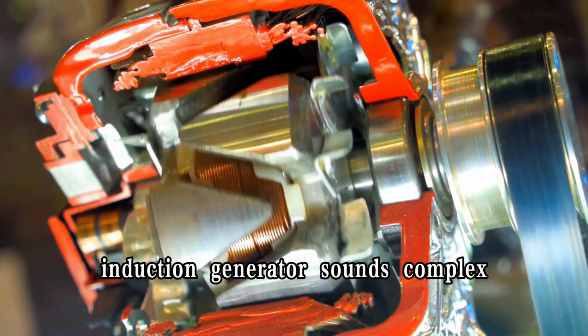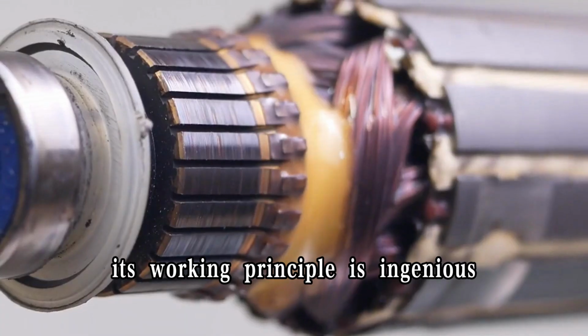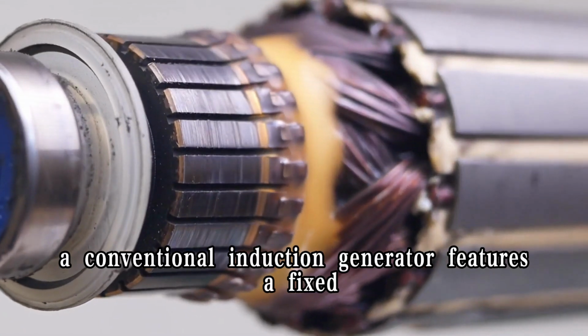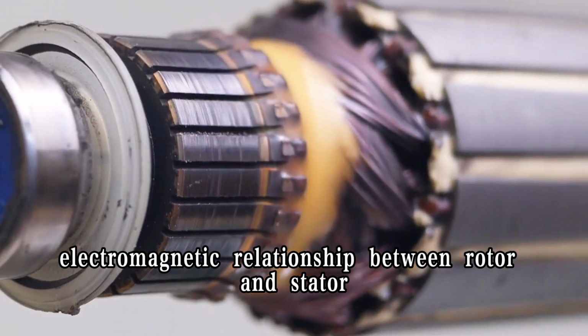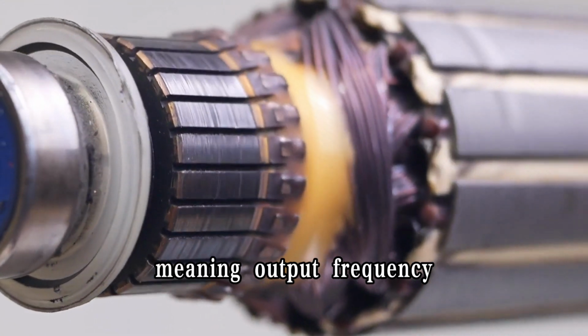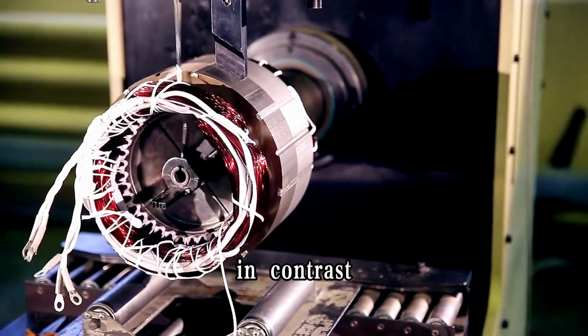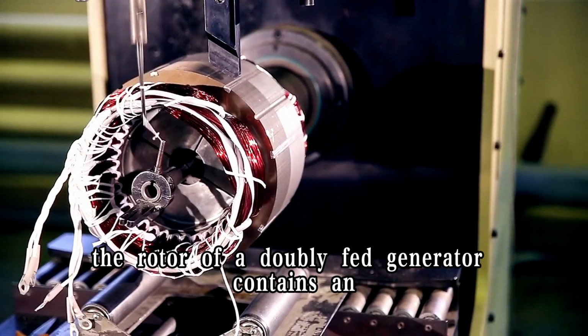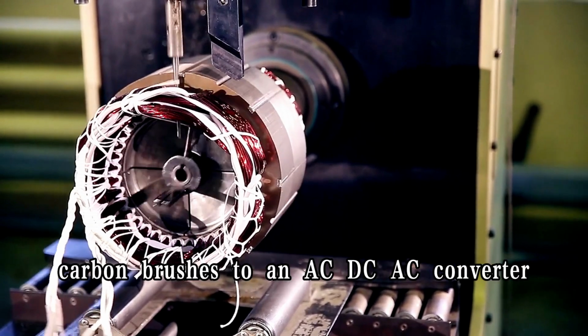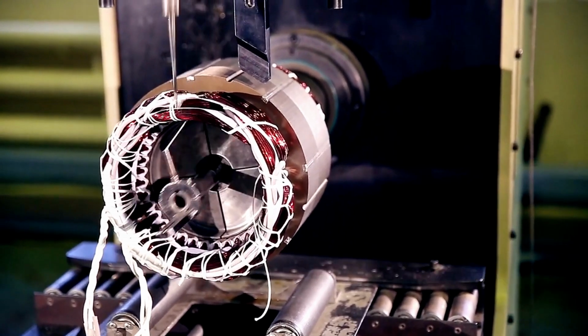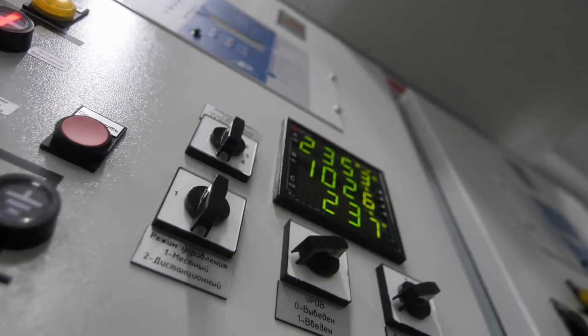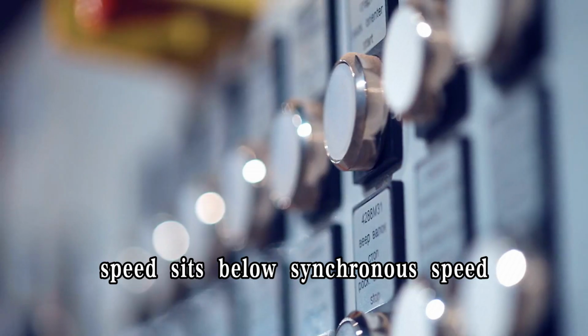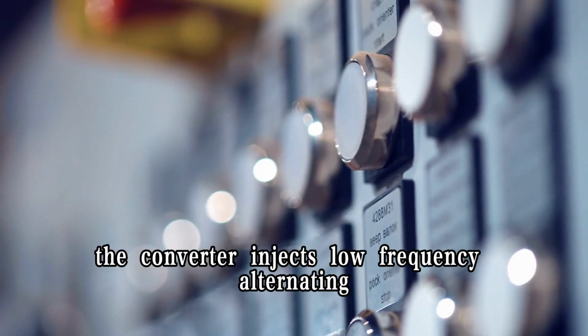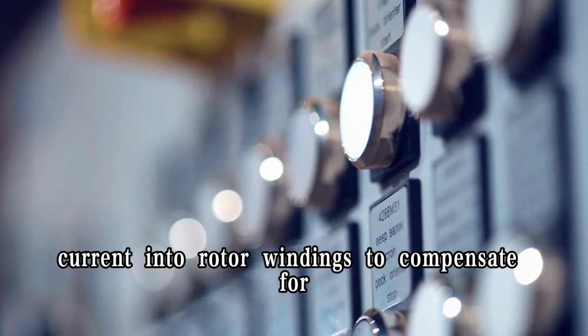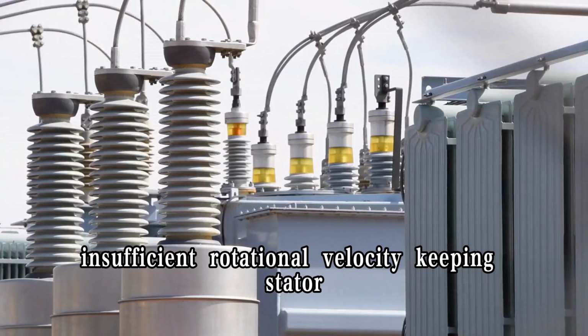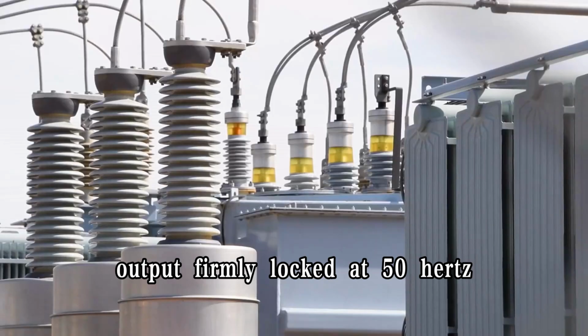Though the name doubly fed induction generator sounds complex, its working principle is ingenious. A conventional induction generator features a fixed electromagnetic relationship between rotor and stator, meaning output frequency fluctuates alongside rotor speed. In contrast, the rotor of a doubly fed generator contains an extra set of coils connected via slip rings and carbon brushes to an AC-DC-AC converter, which acts as a smart frequency regulator. During low wind conditions when rotor speed sits below synchronous speed, the converter injects low-frequency alternating current into rotor windings to compensate for insufficient rotational velocity, keeping stator output firmly locked at 50 Hz.